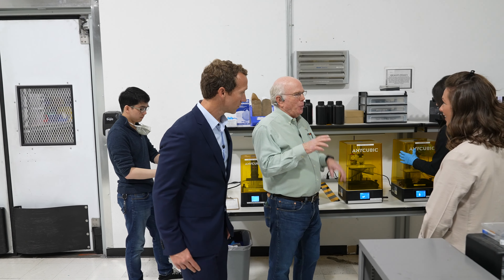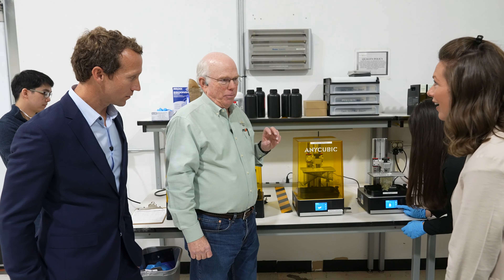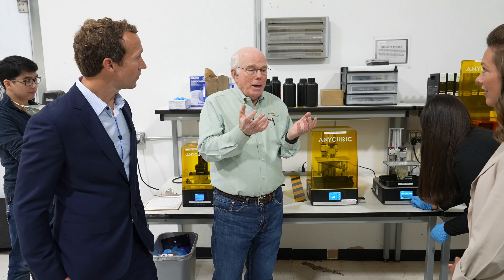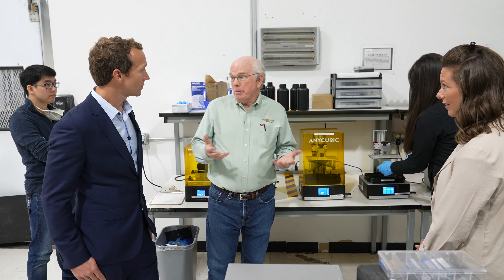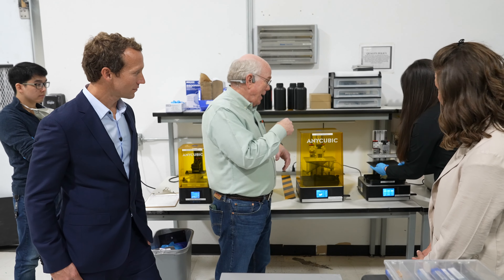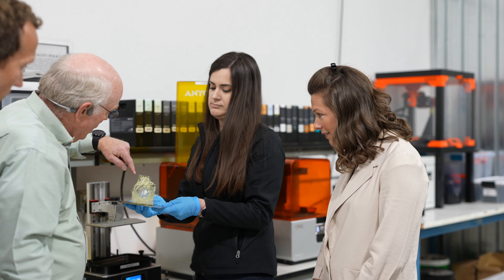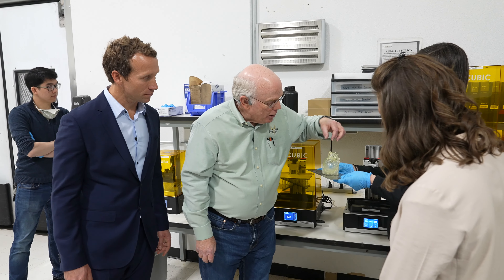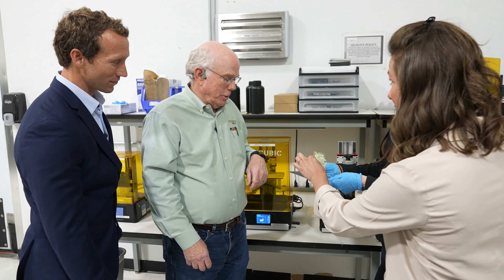Let me show you something just way cool to give a sense of how incredible this digital technology is. Here's a model of a heart. The engineers took this model from online — you can get 3D scans of a heart model, from a real patient's heart, which came from a CT scan. It's a data cloud of all the data points. Then through the software, turn it into — you can see the structure of the aorta coming over here, the various major vessels, the coronary arteries and so on. Is this plastic? Correct. This one is a pliable plastic, not quite like rubber but softer. What are they going to use this for? For testing of a catheter. So you're actually going to stick a catheter through there — the whole heart is hollow.